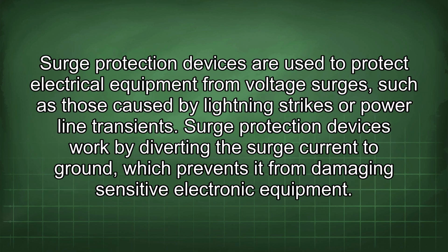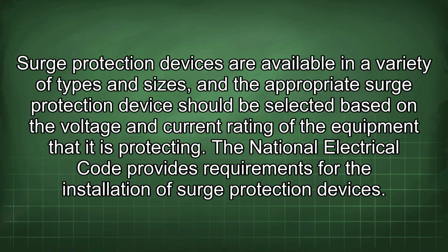Surge protection devices are used to protect electrical equipment from voltage surges, such as those caused by lightning strikes or power line transients. Surge protection devices work by diverting the surge current to ground, which prevents it from damaging sensitive electronic equipment. Surge protection devices are available in a variety of types and sizes, and the appropriate surge protection device should be selected based on the voltage and current rating of the equipment that it is protecting. The National Electrical Code provides requirements for the installation of surge protection devices.